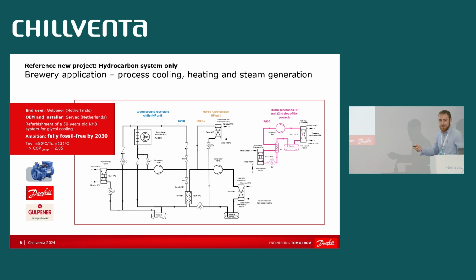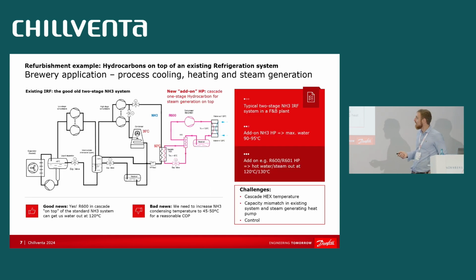This looks nice. It's a very flexible system. You can have only cooling or only heating. You can switch stages on and off, make load balancing. But it's good because it is a greenfield project. It's a new project. Most of the projects are not really there. A typical system in an existing brewery or another food and beverage site would be the good old ammonia 2-stage system, a fantastic refrigerant for cooling.